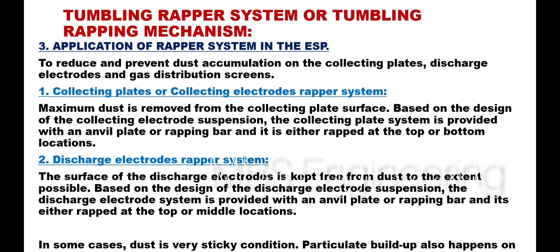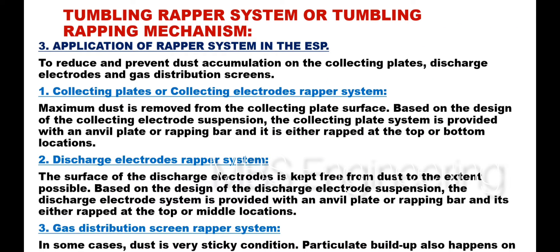For the discharge electrodes rapper system, the surface of the discharge electrodes is kept free from dust to the extent possible. Based on the design of the discharge electrode suspension, the discharge electrode system is provided with an anvil plate or rapping bar, and it is either rapped at the top or middle locations.